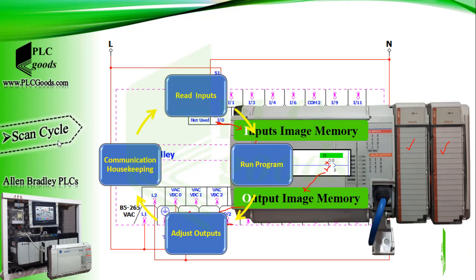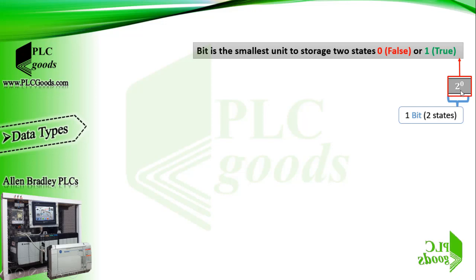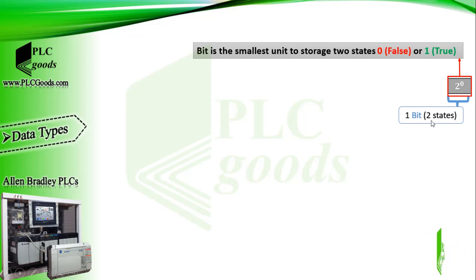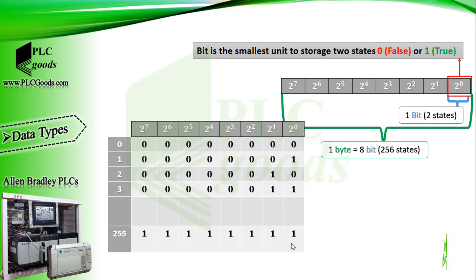In an industrial process the user program needs to know equipment and signal status. A bit is the smallest unit of storage with two states: zero (false) or one (true). A digital input only has two states, so it needs one bit in PLC memory. If we have eight bits it's called a byte. One byte can store 256 states — from zero with eight zeros, up to two hundred and fifty-five.